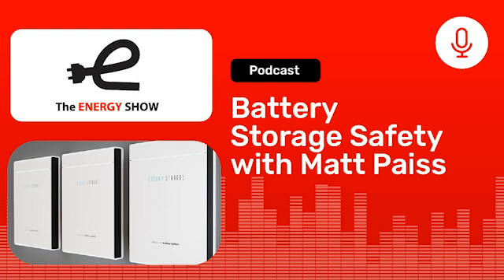The location of the battery is very important, and that's location-dependent across the country as well. An outdoor installation here in California is pretty easy, a good environment. But in areas like Phoenix, that might not be a great idea. A garage in Phoenix might be a bad idea, or outside in New England might be bad because of snow. So it's a delicate solution that has to be addressed location by location.